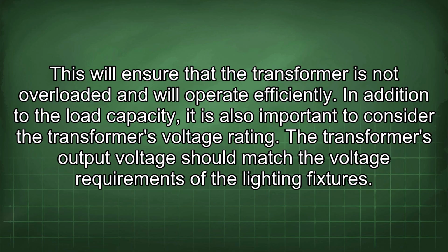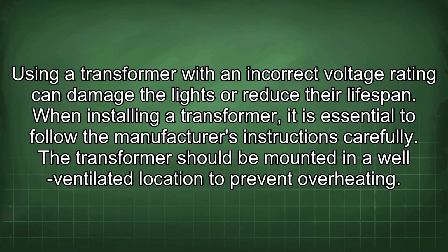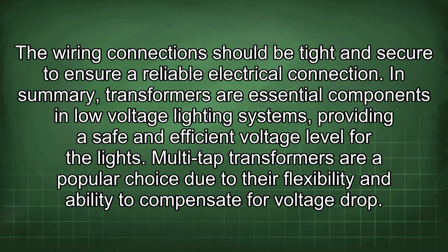In addition to the load capacity, it is also important to consider the transformer's voltage rating. The transformer's output voltage should match the voltage requirements of the lighting fixtures. Using a transformer with an incorrect voltage rating can damage the lights or reduce their lifespan. When installing a transformer, it is essential to follow the manufacturer's instructions carefully. The transformer should be mounted in a well-ventilated location to prevent overheating. The wiring connections should be tight and secure to ensure a reliable electrical connection.